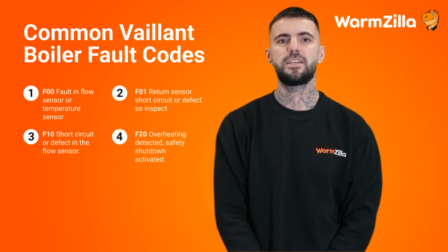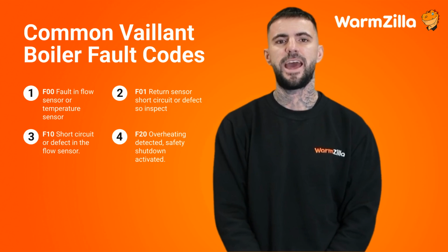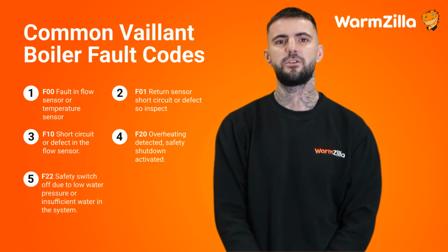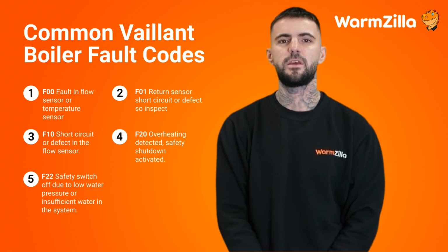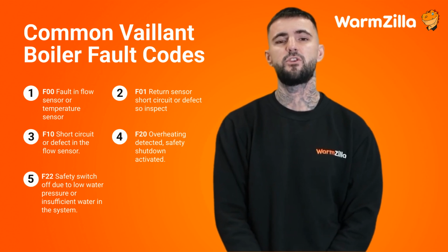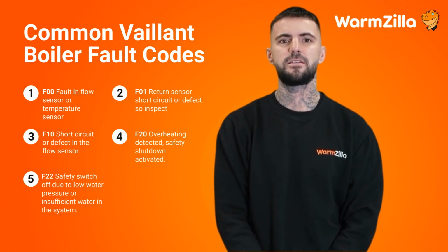Fault code F20 shows that overheating is detected and safety shutdown is activated. You'll need to allow the boiler to cool, check water circulation, and inspect the thermostat. F22 is the safety switch off due to low water pressure or insufficient water in the system. Just refill the system to the correct pressure and check for leaks.